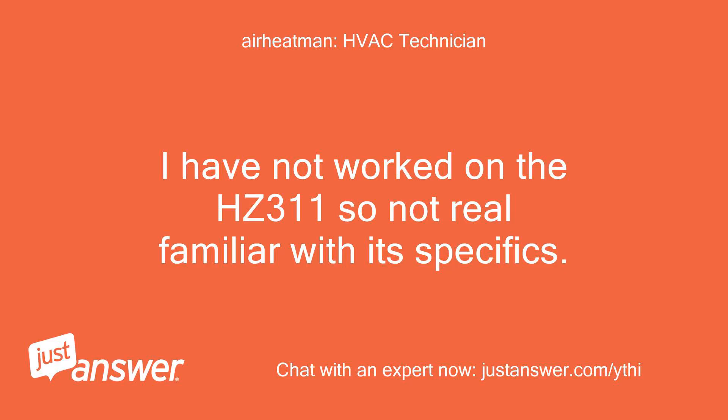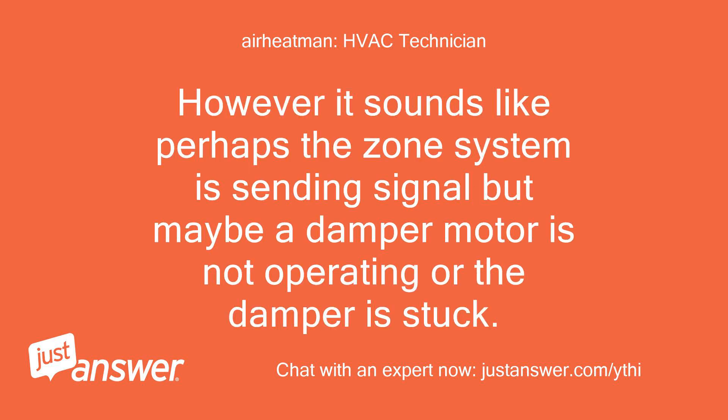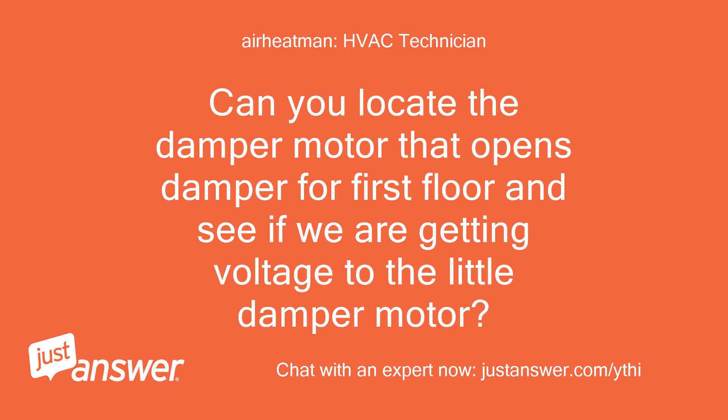I have not worked on the HZ311, so not real familiar with its specifics. However, it sounds like perhaps the zone system is sending a signal but maybe a damper motor is not operating or the damper is stuck. Can you locate the damper motor that opens the damper for the first floor and see if we are getting voltage to the damper motor?